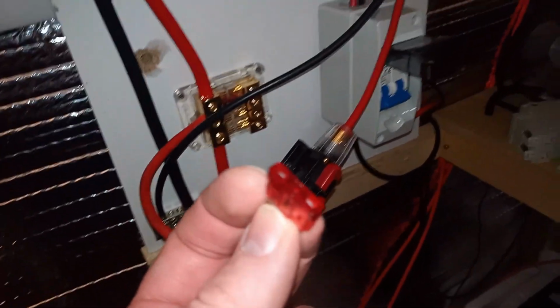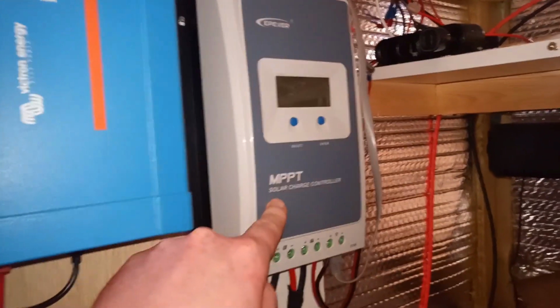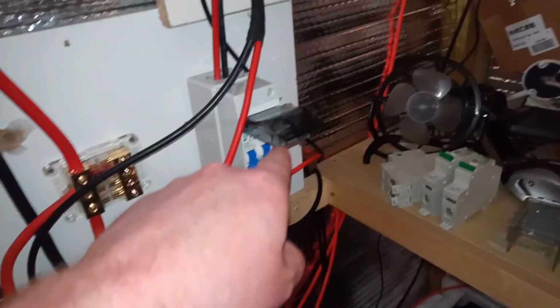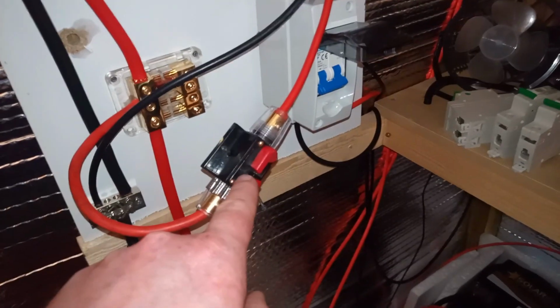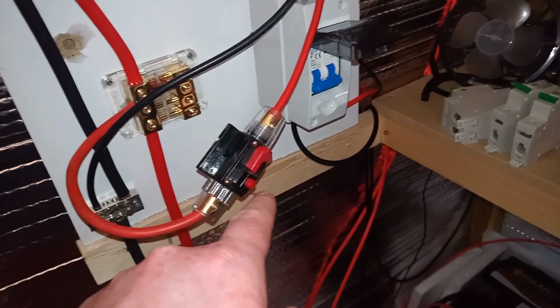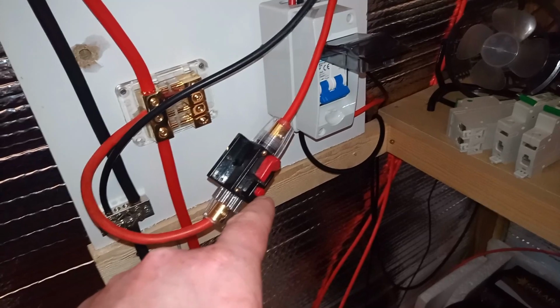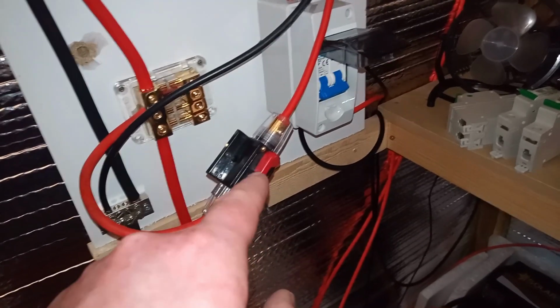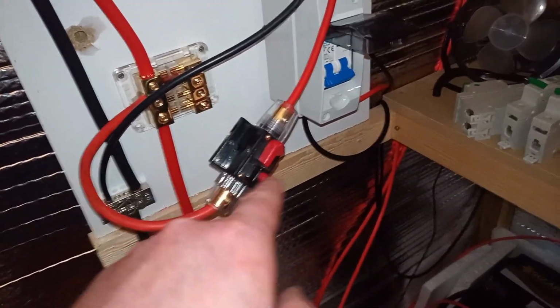Heard it pop. It was a 10 amp fuse, going to the 10 amp charge controller. The old one. Yeah, I changed the cable. I've added a breaker for the panels. DC breaker. Because I was using one of these, that one, and it wasn't sufficient. So the breaker I had for the panels is now temporarily wired in because the fuse is blown.